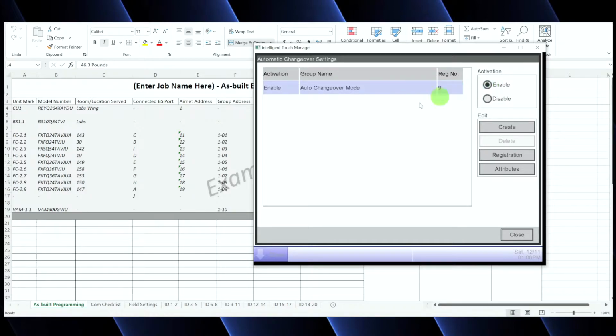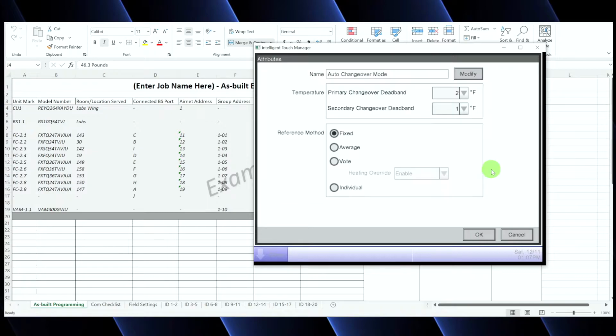And so now all of these indoor units will automatically be controlled individually based on our auto changeover setup. Now there's one more thing we have to do, and we have to actually set up how many degrees past the set point we want to allow the room temperature to get before it starts that guard timer that we briefly just spoke about, and then eventually switching modes. So we're going to go to attributes.